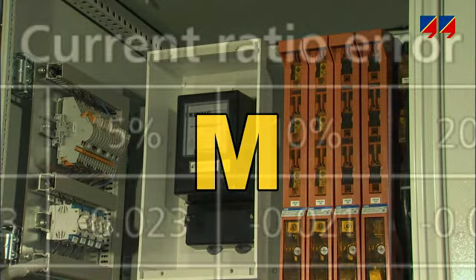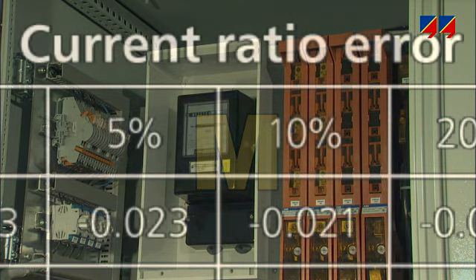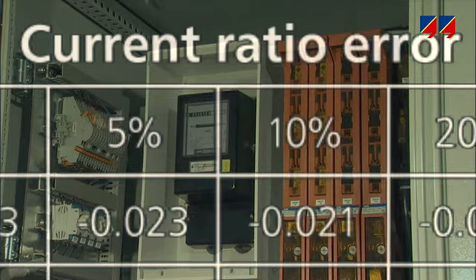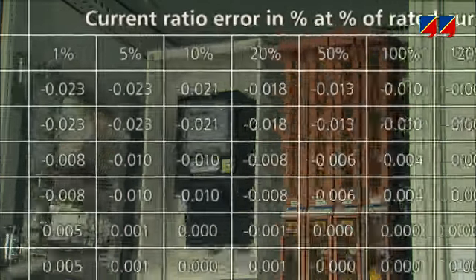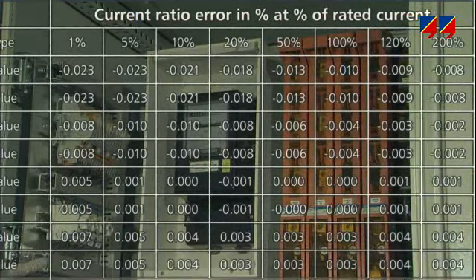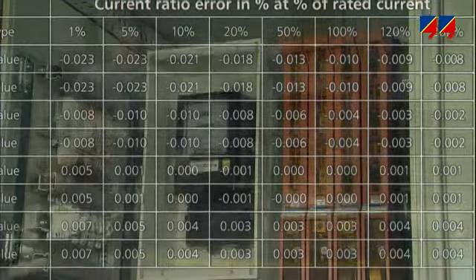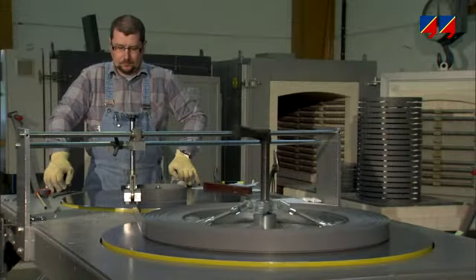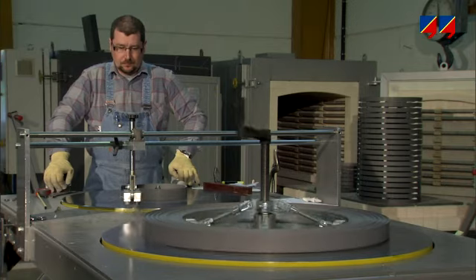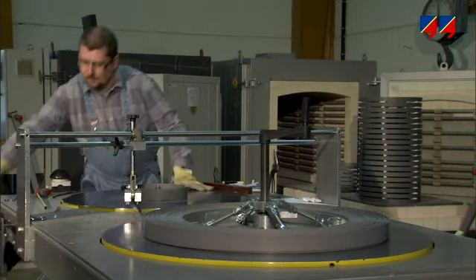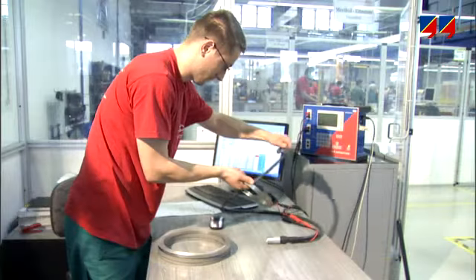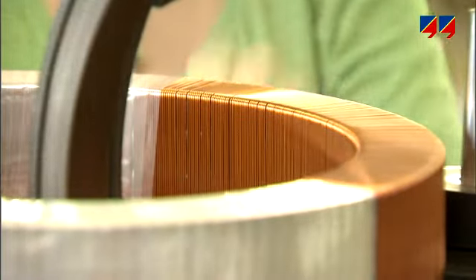Accuracy is the crucial criterion regarding metering CTs, as the financial consequences of incorrect billing may be very significant. The applicable standards define the ratio and phase accuracy which the CT has to provide in its specified operating range. In order to ensure reliable protection and correct metering, CTs must be tested at several stages during their life cycle. Manufacturers verify the required parameters during design and manufacturing.